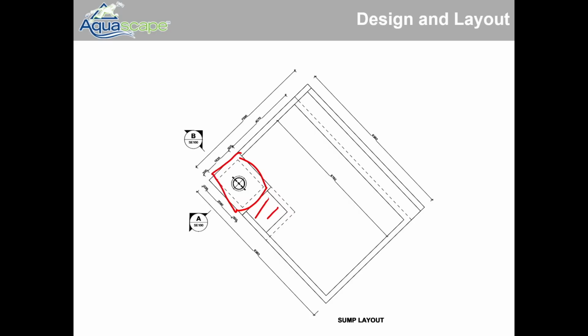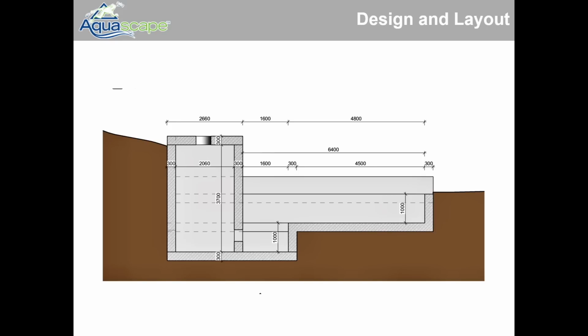These are huge, high horsepower pumps, and they have a minimum submergence level. So I want to make sure that these pumps are always going to be underwater, which is why this pump vault, if we look at our next drawing, is actually over 12 feet deep. So from grade over here all the way to the bottom, that's 12 feet. It's a massive column of concrete going all the way down to the bottom.